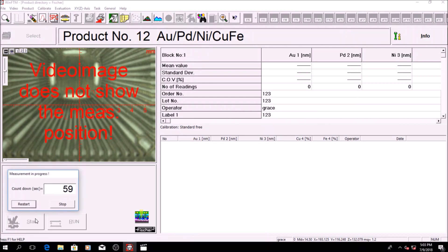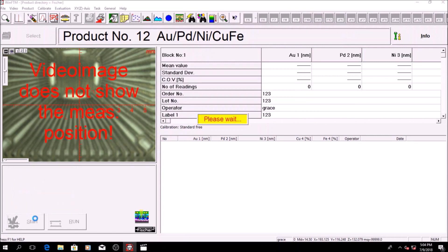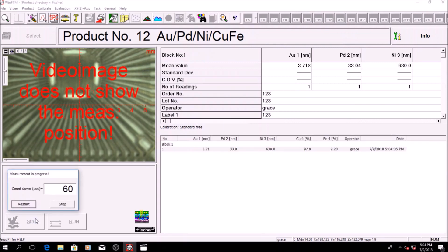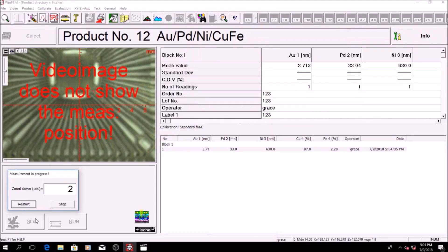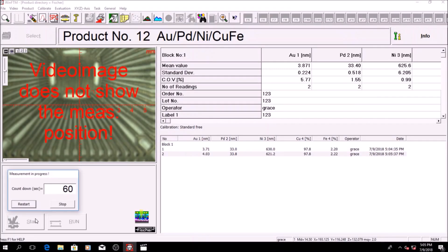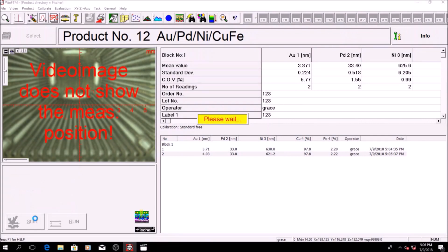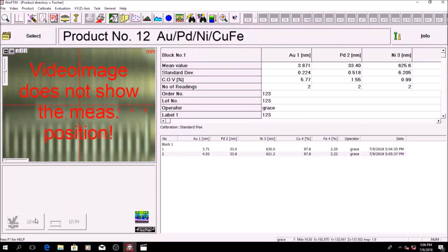Fischer x-rays are known for accurate standard free measurements. This is particularly useful when calibration standards are not readily available. But to get the highest performance, corrective calibration should be performed to adapt to the substrate material, shape of specimen, and a particular coating thickness level.